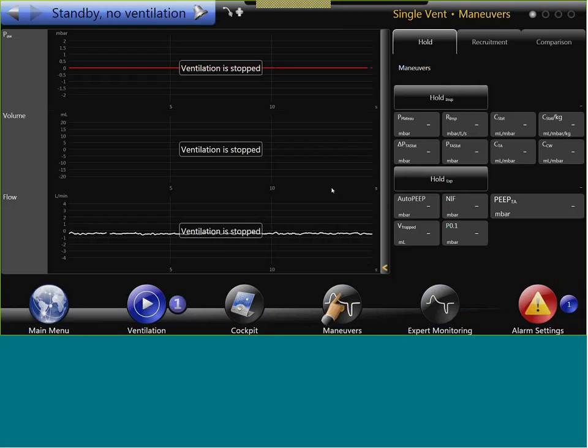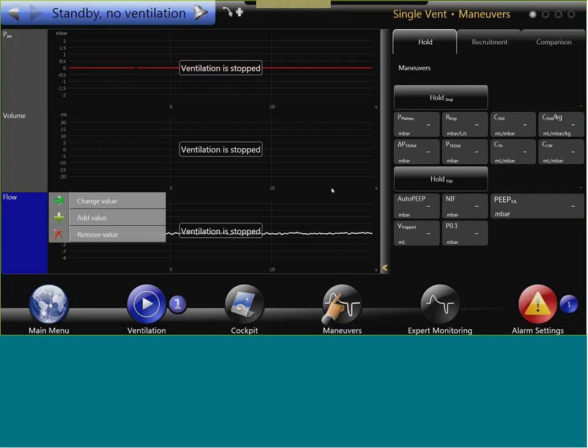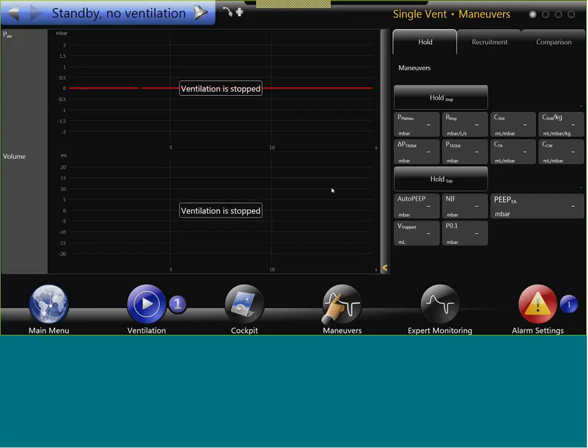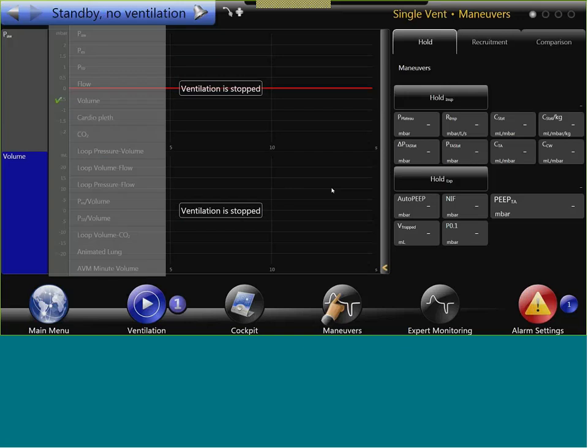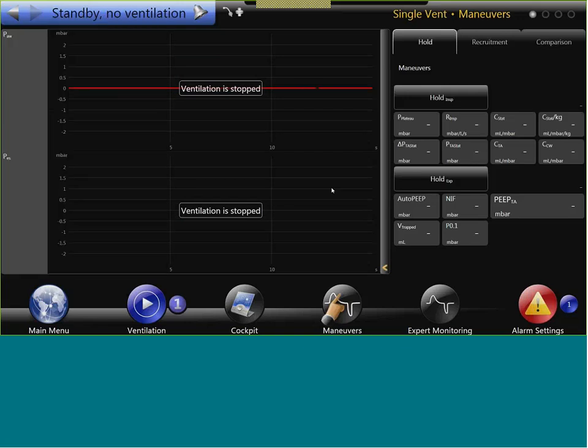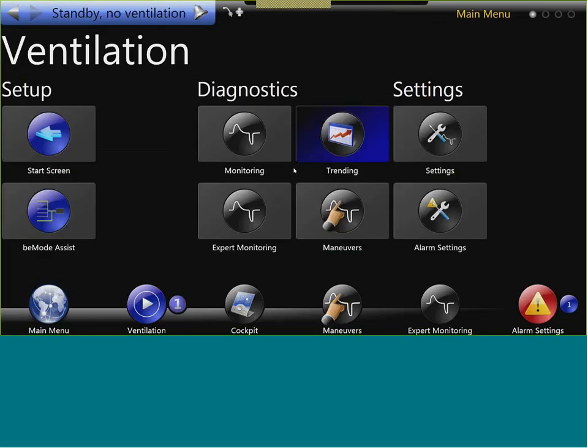And you can configure this screen, and it will be a persistent setting, so it will stay forever, but it won't be taken over into the profile. So if you want to have a screen like this, and I say, okay, I just need Paw and volume, for example, or I would like to see, for example, esophageal pressure, you can configure this, and this will stay, but not in the profile.